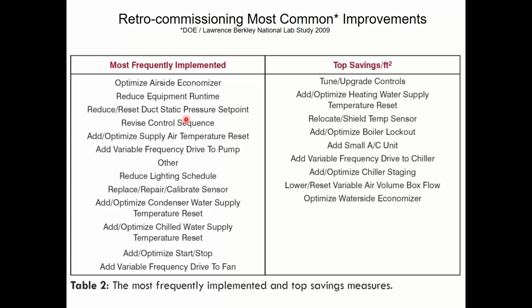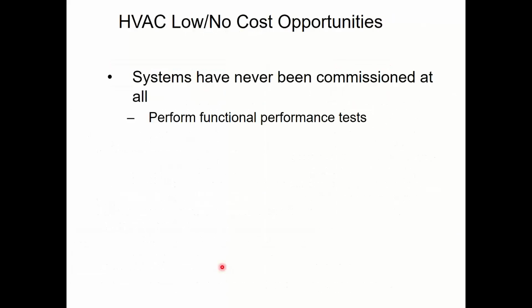So some of the top things that can be fixed on existing buildings: fixing the air side economizer, which we're going to talk about today; reducing equipment runtime, which is kind of a no-brainer, but people don't do it. Other ones that might apply to package systems like we're talking about today. My mouse froze up there. Repairing, replacing, calibrating sensors applies to package systems. Optimal start routines apply to package systems. VFDs can apply to package systems. So there are several of these on the list that we can do for the building types that we're talking about. A lot of what we're going to do is going to come from the control standpoint.